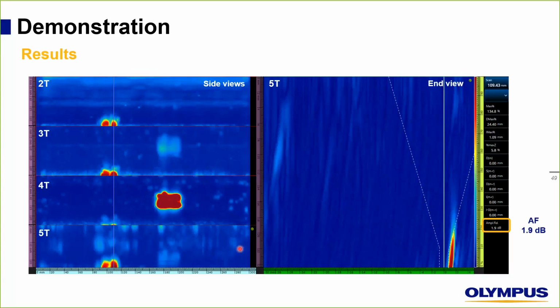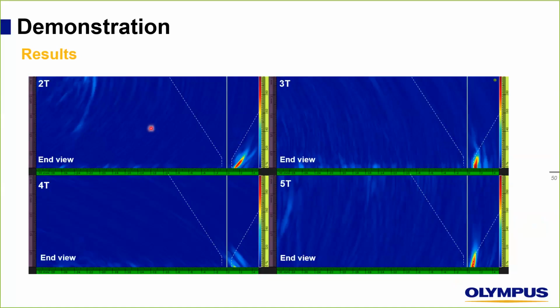Actually, in the OmniScan, you can recognize your main end view on the screen just by having a look at the green dot here that corresponds to the green dot there. So here we are looking at the 5T. I selected the 5T just to see how straight the indication is, so it corresponds to the orientation of a crack. If we go to the next slide, as we said, we detected it with the 2T, the 3T, the 5T, and a very slight indication in the 4T. The difference between the 2T and the 3T or 5T is the orientation. The 2T is like standard phased array, so the orientation of the indication here is not straight as the root crack should be, but with 3T we have a better imaging of that crack.